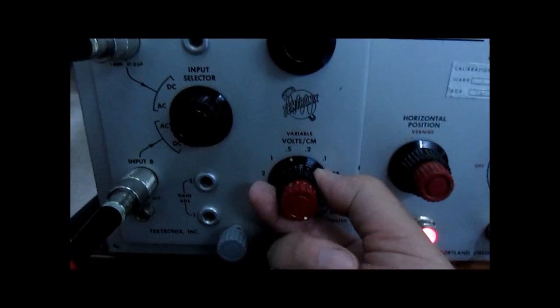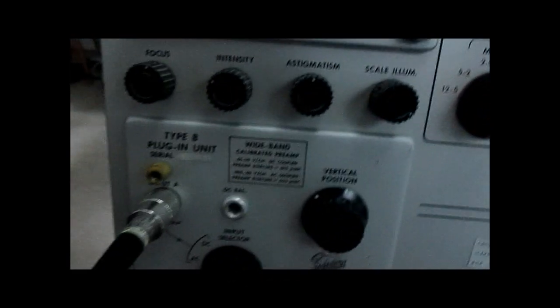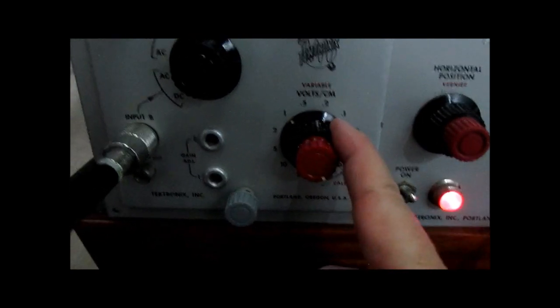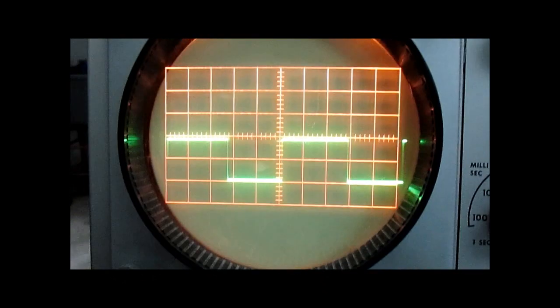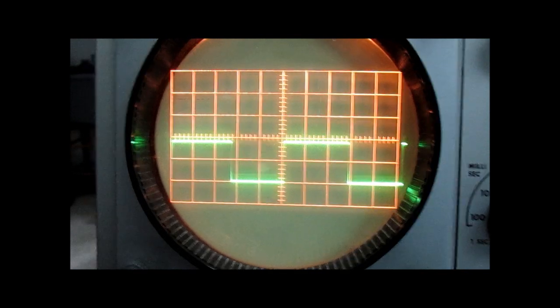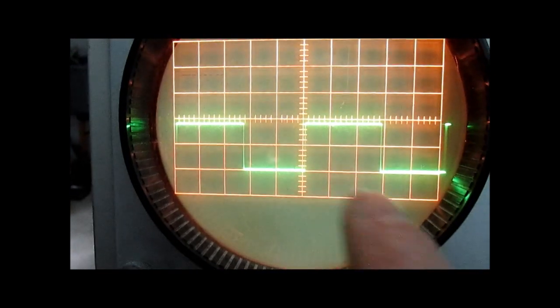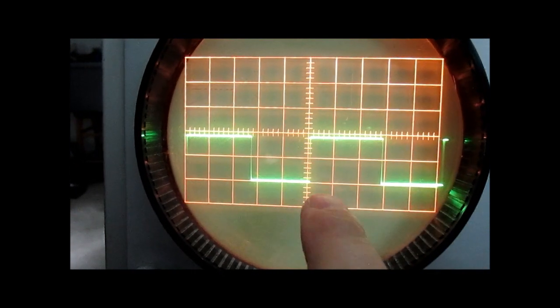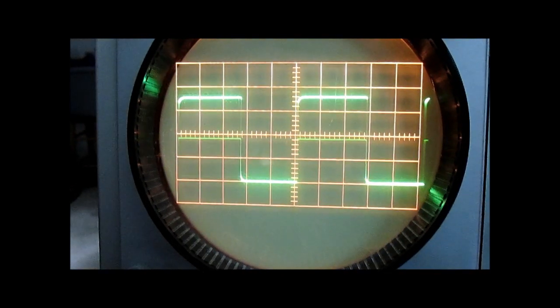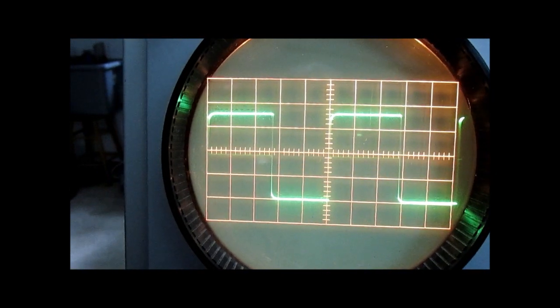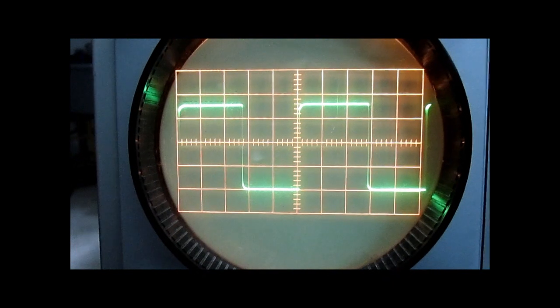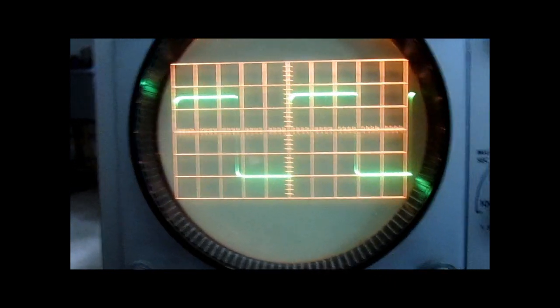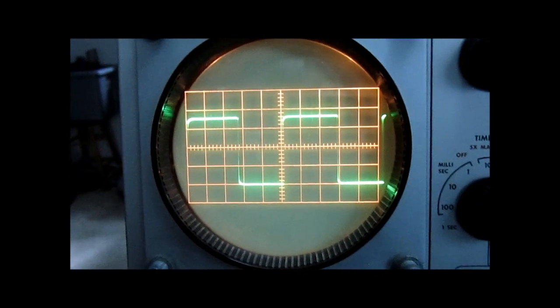So let's turn that down so that we get half of that. So now we still have the 20 volts peak to peak, but now this is set for 10 volts per division, and that one looks a little closer. And you also notice that the edges of the square wave are squarer than they were here. So there's some problems with the compensation networks on the attenuator inputs of our plug-in, and you'll really see that on some of the other ranges.